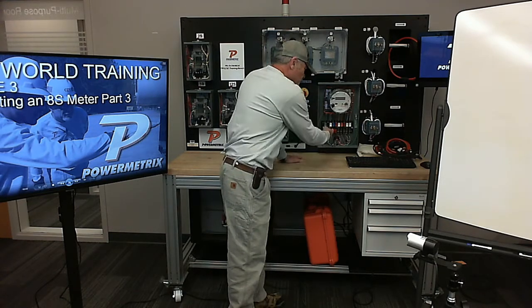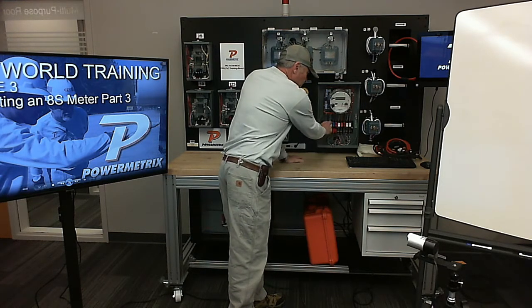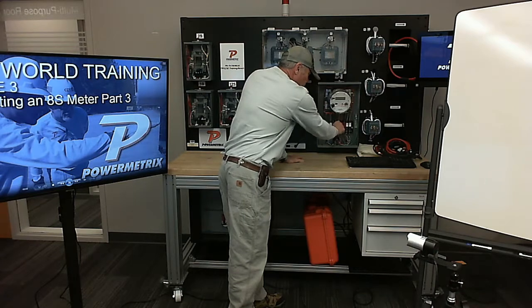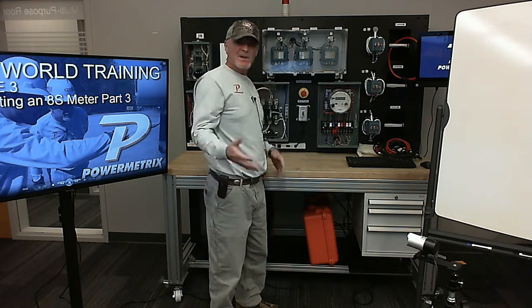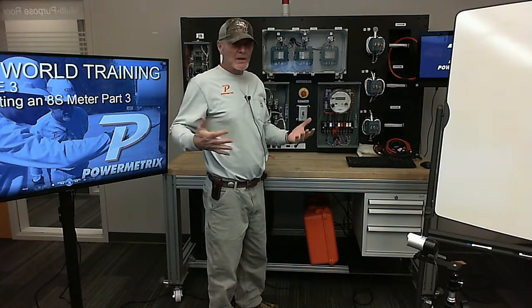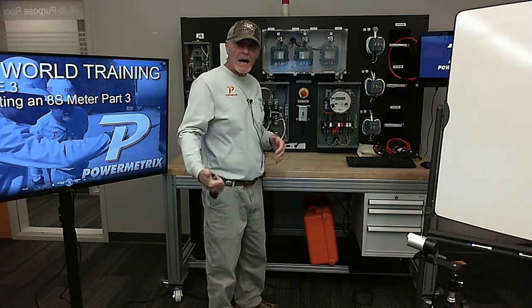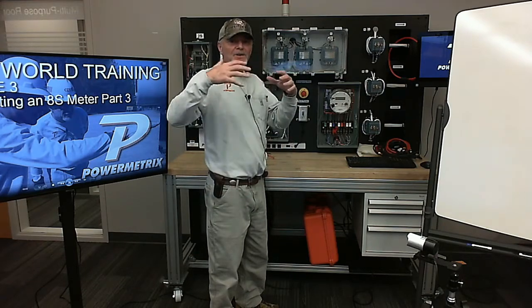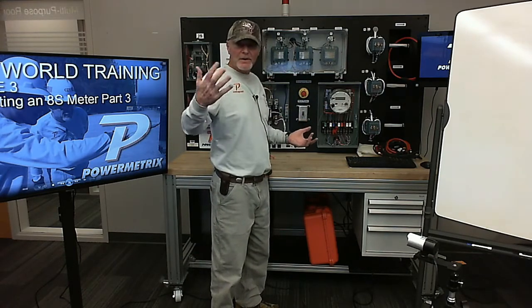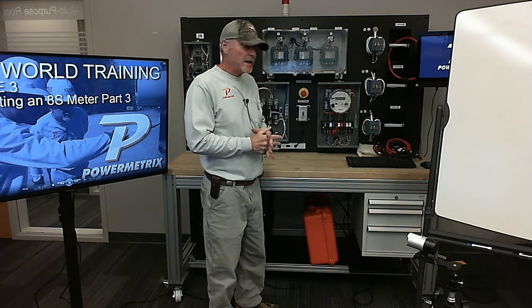Remember, it's a short stroke on the next phase—that's A phase—so when you get over to B phase, it doesn't mess with it. It's these little things, but they can keep you from trouble, because usually when it's scalding hot, mosquitoes swarming around your head, and you're trying to get the test done, you don't want the nuisance of knocking your voltage alligator clips off.